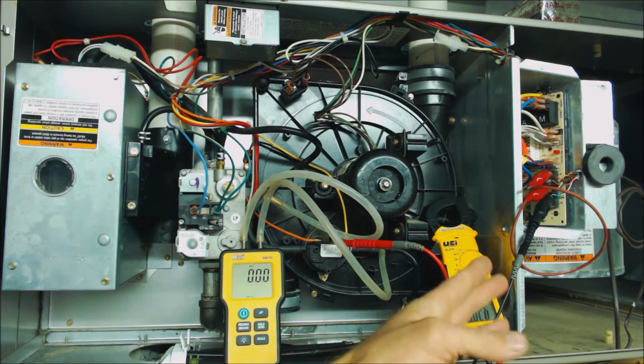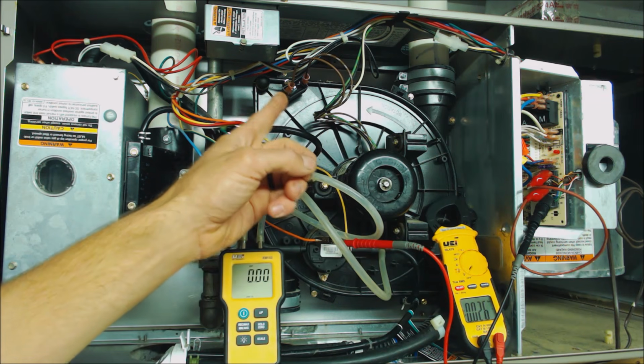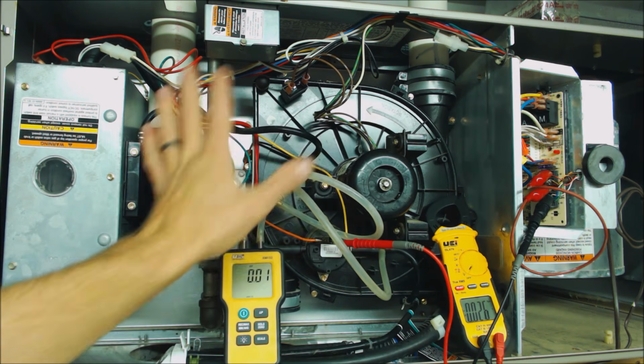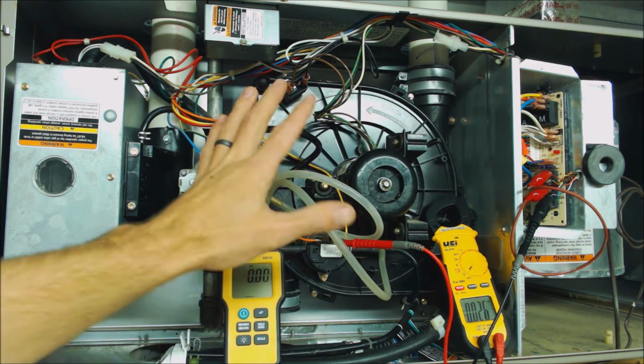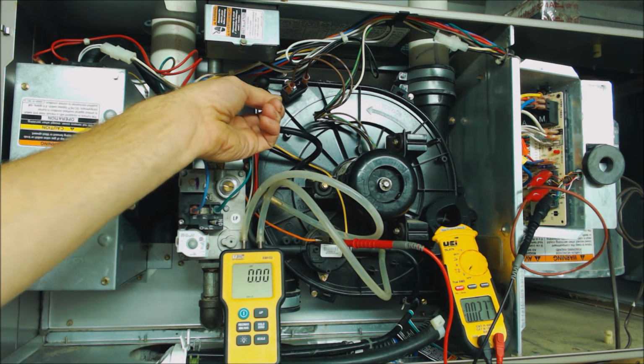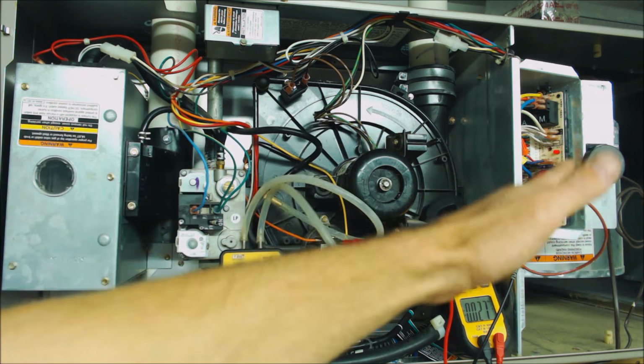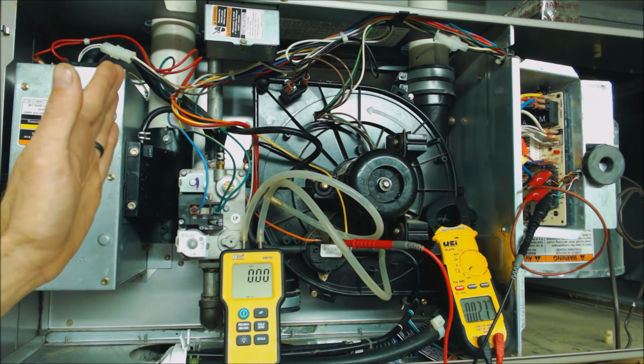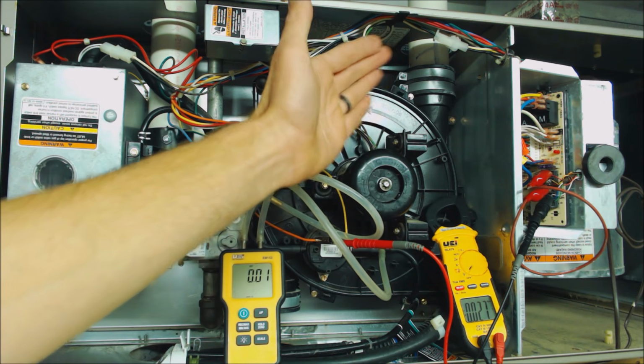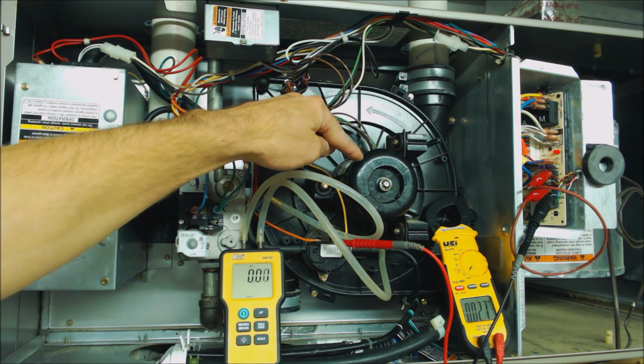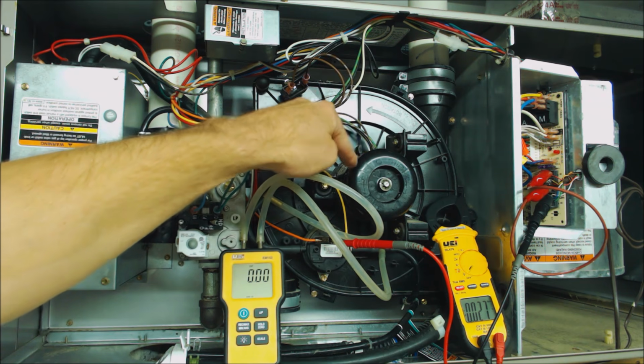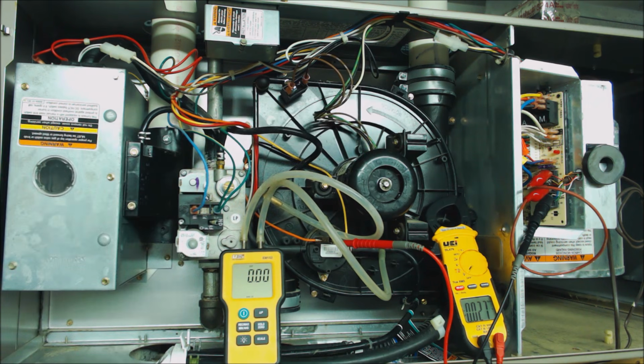The reason that the blower motor is on is this furnace was turned off in the middle of its heat sequence last time, so the furnace itself does not know if the heat exchanger is really hot. So the blower motor is going to go ahead and cool the heat exchanger down before the sequence of operation starts, which the first thing that will happen is this inducer motor is going to turn on. So I'm going to go ahead and fast forward through this.